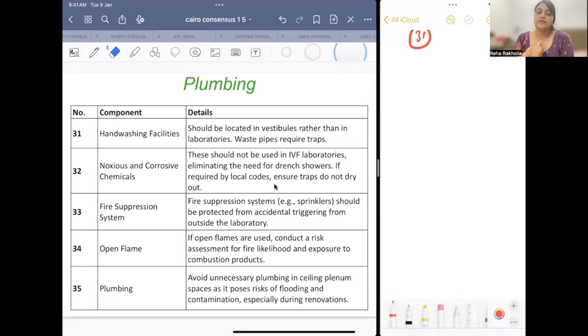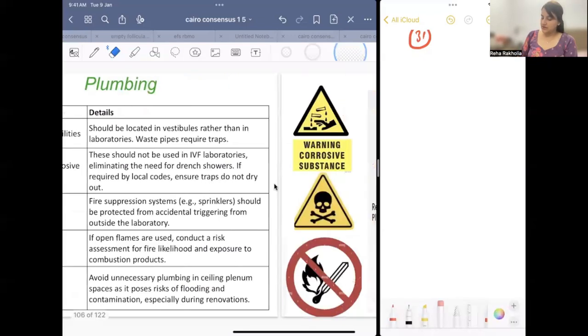Plumbing. We do not use plumbing in the plenum; in the IVF lab, we use closed plenum. Okay, plenum is the area above the ceiling where filters and all those things are kept. That is called plenum. So basically, we should not use plumbing in the plenum. Avoid unnecessary plumbing in the ceiling plenum spaces, as it poses risk of flooding and contamination, especially during renovation.